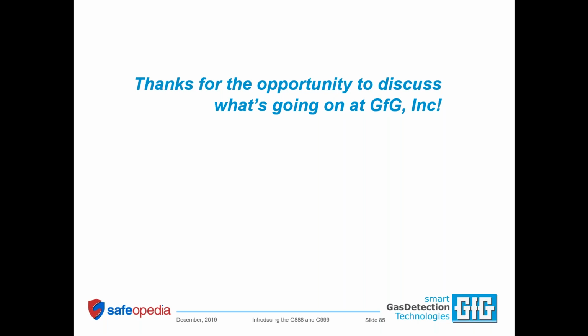Is the rechargeable battery pack field replaceable? Yes, it is, but it's going to be different than you're used to with the 450 and the 460. With the 888 and the 999, 4 screws hold the back of the instrument in place, and we actually replace the whole back cover. The rechargeable battery is encapsulated in the back of the instrument, so you don't replace the battery pack by itself, you replace the back of the instrument. But it's affordable, you don't pay a penalty for taking that approach, and it makes it really easy.